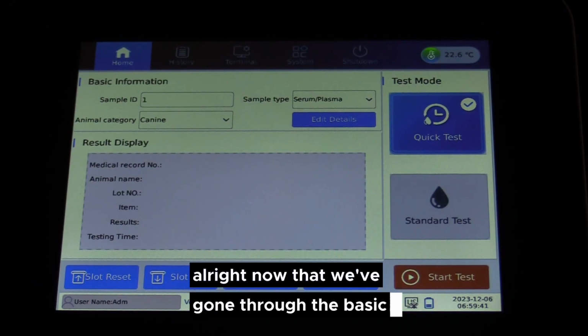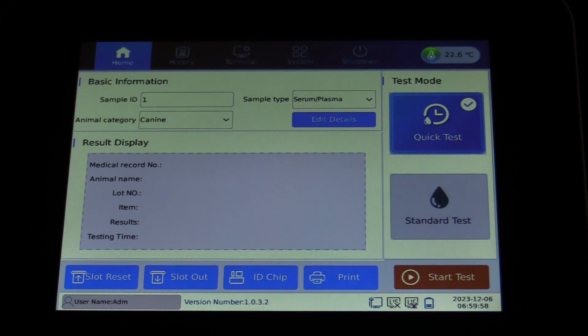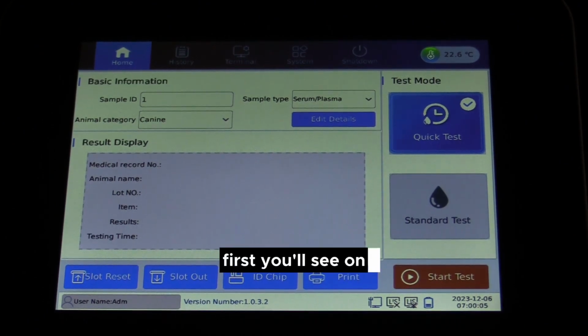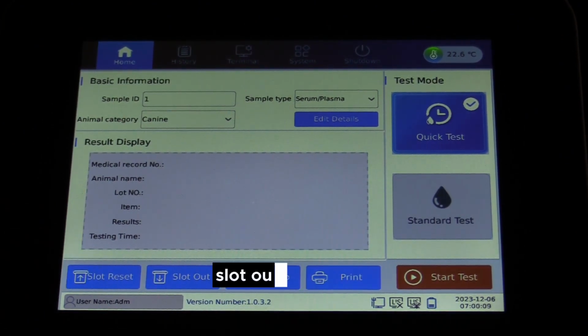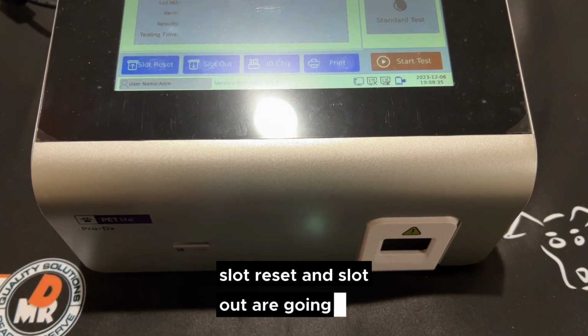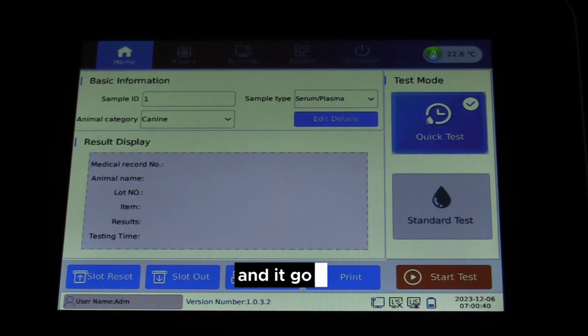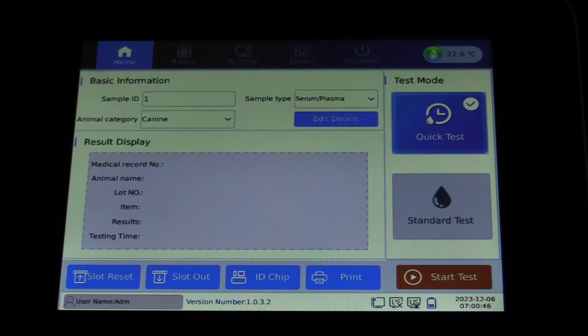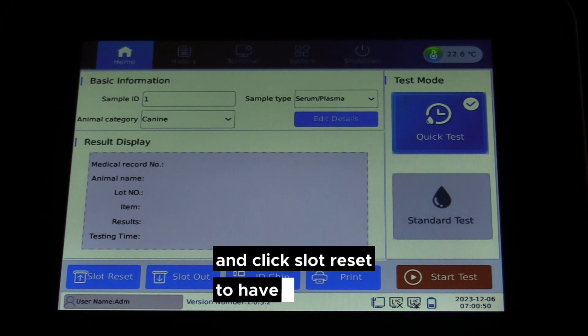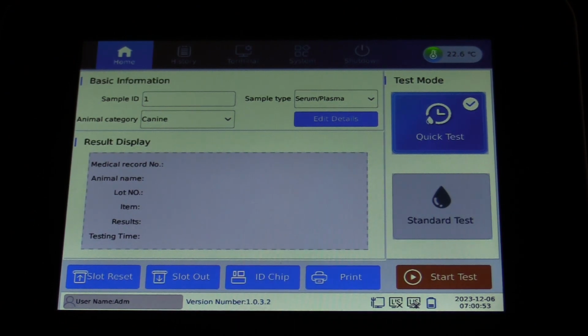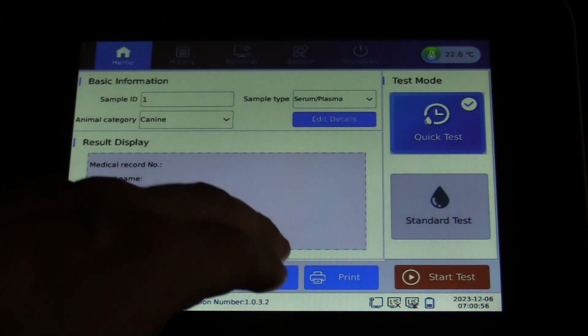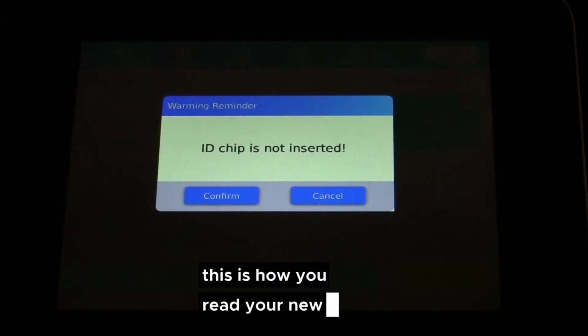All right, now that we've gone through the basics of the machine, let's take a look at the menu. Now the menu is very similar to the old Finecare unit, however there are some changes I would like to point out here. First, you'll see on the front page, slot reset, slot out, ID chip, print, and start test along the bottom. Slot reset and slot out are going to reset the transport. That's the piece that we're showing here that you place the test cartridge in, and it goes into the machine. So to get it back out, click slot out and click slot reset to have it go back in. As we mentioned in the calibration portion, ID chip, you press this is how you read your new ID chip.